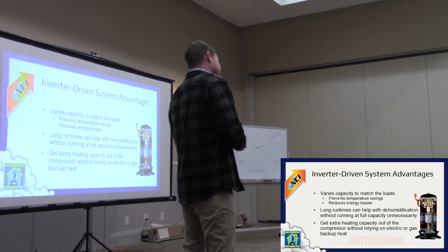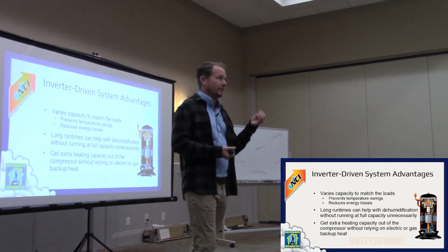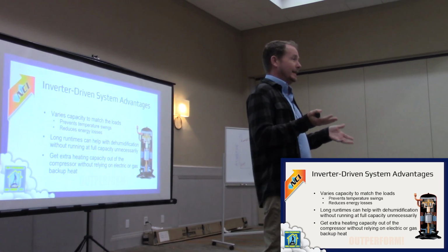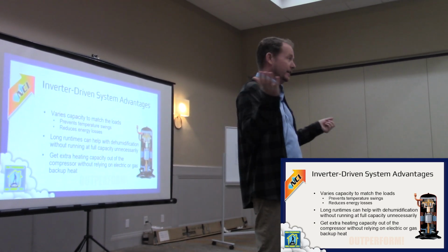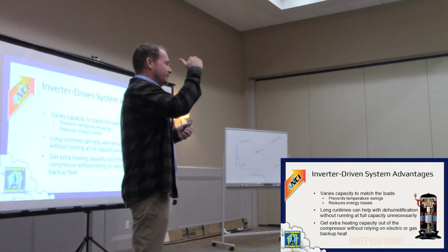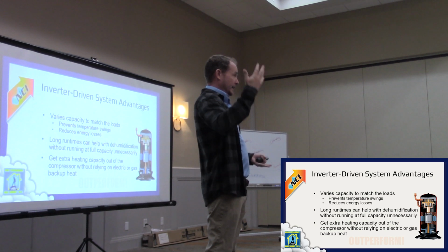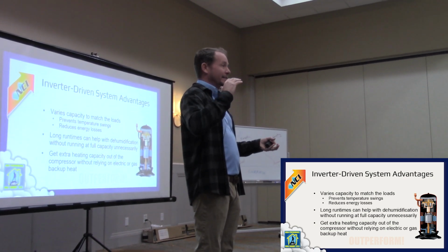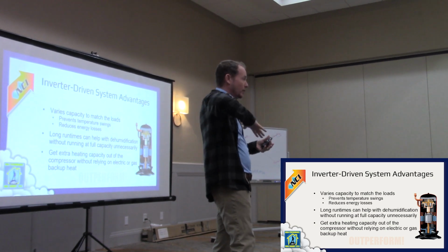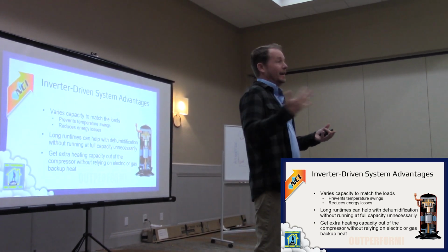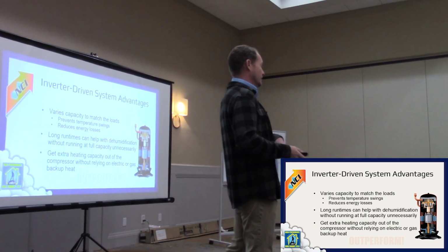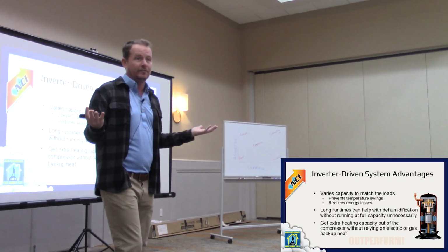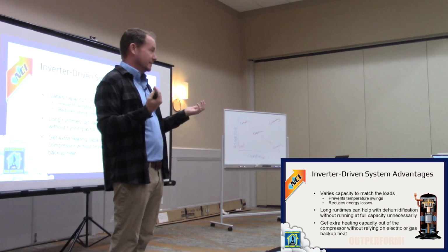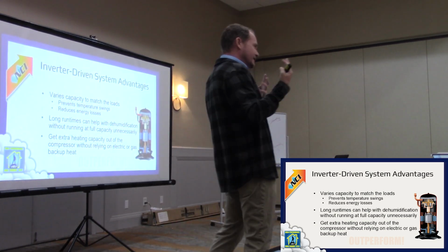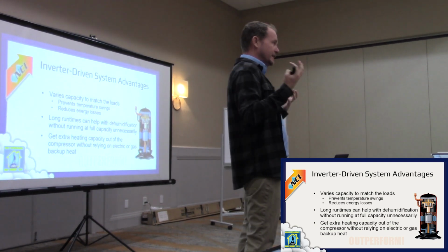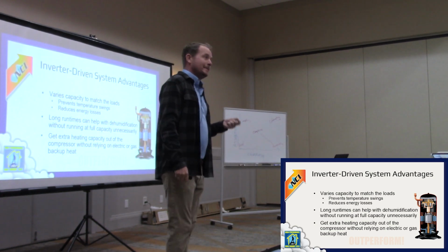That's good, but there are other issues. Oil return can become a problem, because systems were designed with pretty fixed velocities and mass flow rates through the lines, and now you're varying that a lot. You don't want to put in something that's improperly sized and turned down all the time, running real slow, because you'll get oil return issues. Manufacturers like VRF and VRV, with miles of copper throughout a building, have to mitigate this by driving the system into high speed to get the oil back, or pumping liquid through the lines. These are design challenges, and sometimes manufacturers handle them well, sometimes they don't.